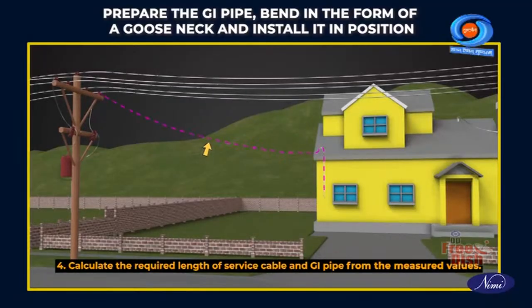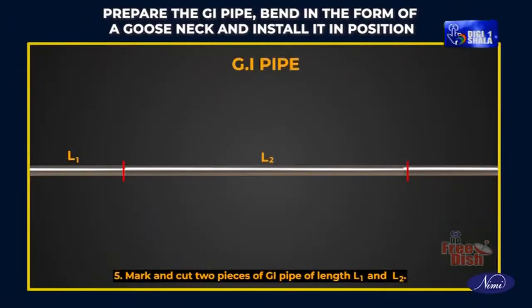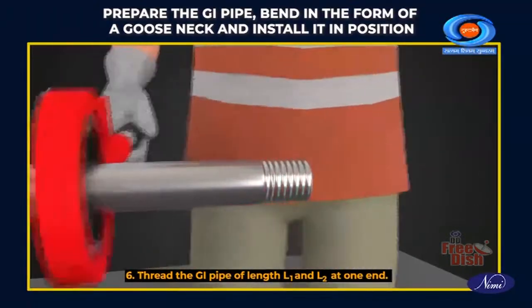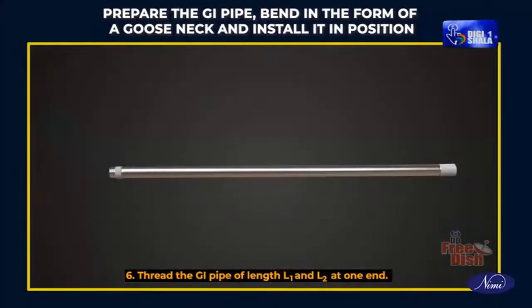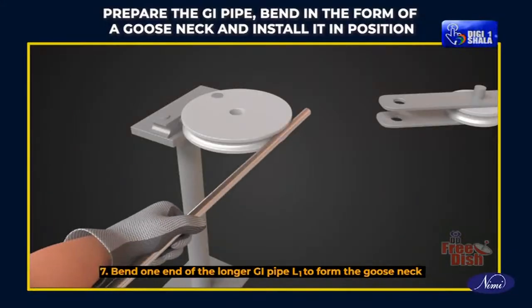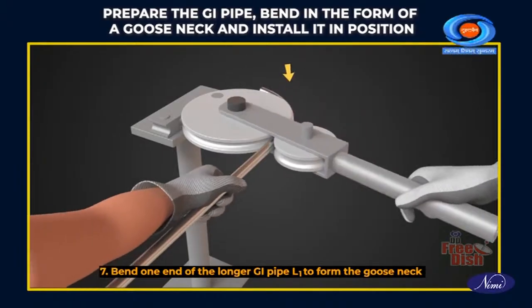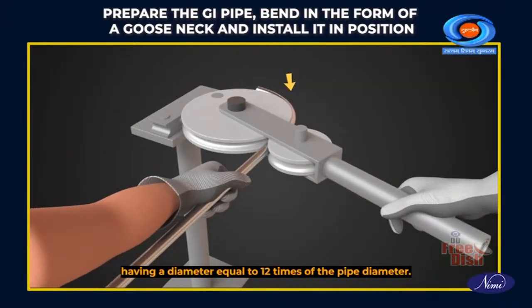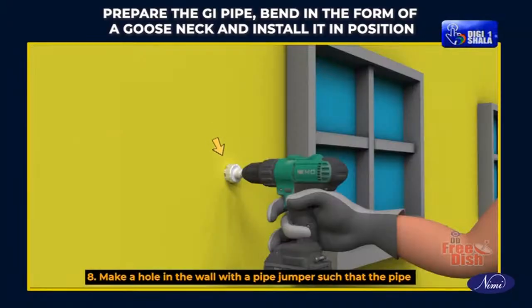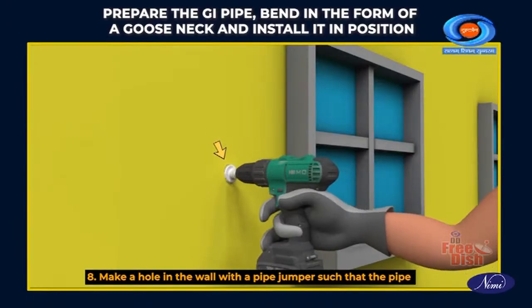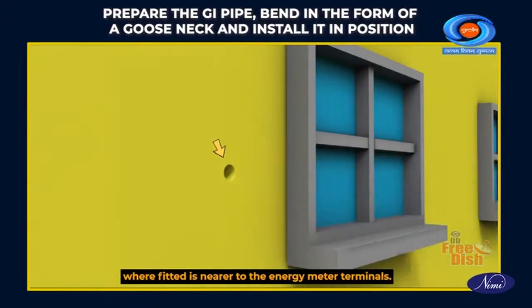Calculate the required length of service cable and GI pipe from the measured values. Mark and cut two pieces of GI pipe of length L1 and L2. Thread the GI pipe of length L1 and L2 at one end. Bend one end of the longer GI pipe L1 to form the gooseneck having a diameter equal to 12 times of the pipe diameter. Make a hole in the wall with a pipe jumper such that the pipe where fitted is nearer to the energy meter terminals.